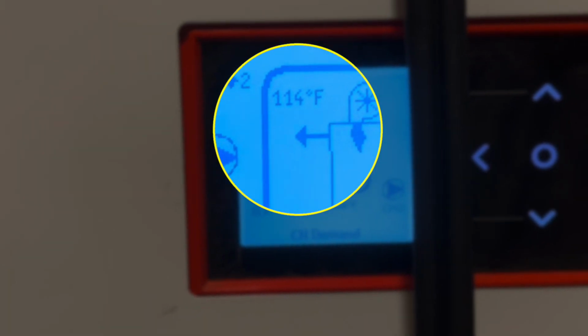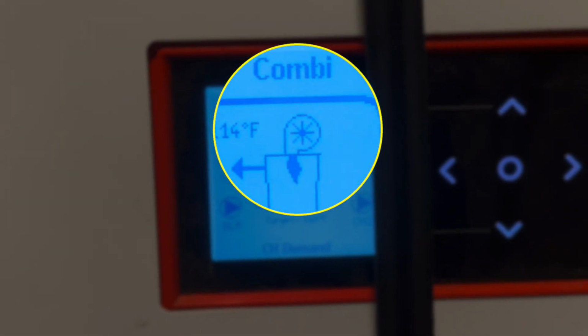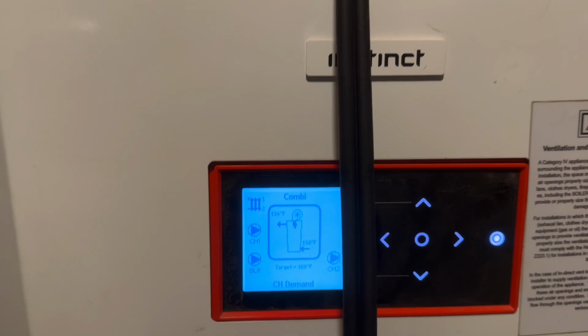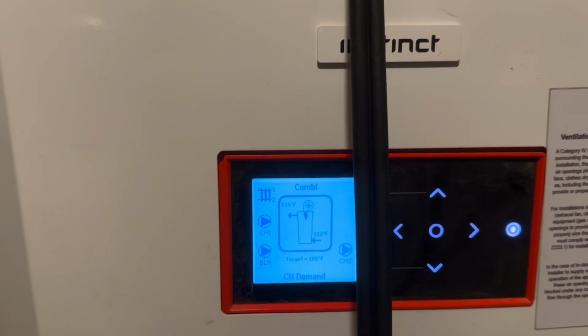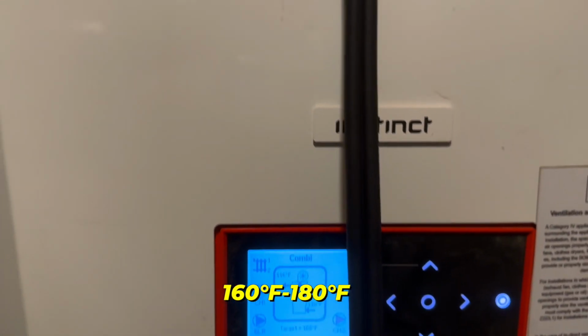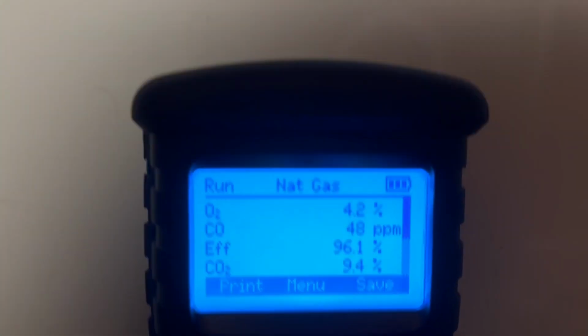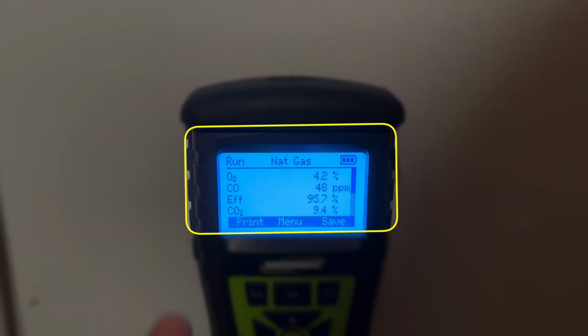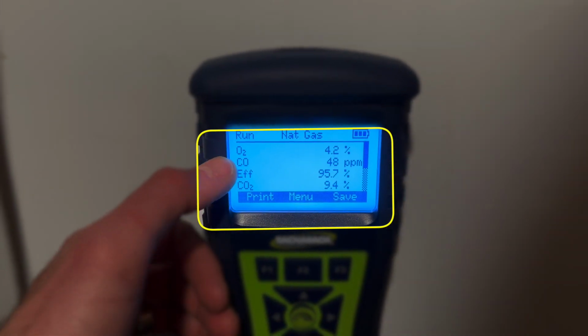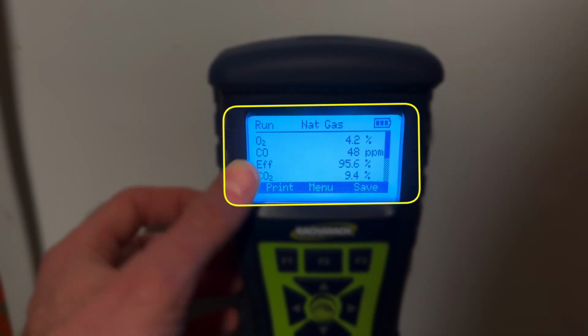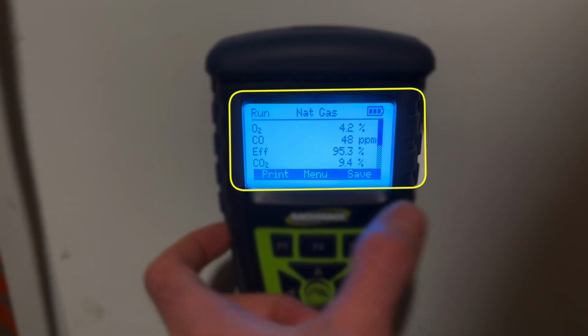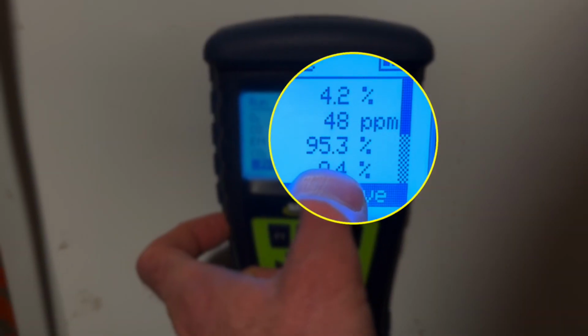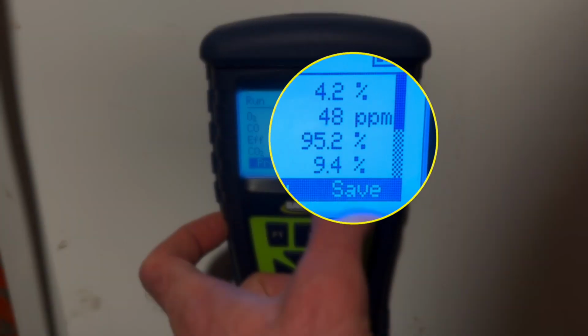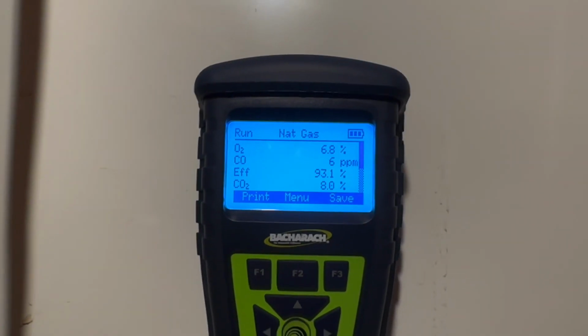So it's firing at 114 on your supply and 106 on the return. And the boiler's actual operating temperature is going to be around 160 to 180, depending on how you have it set up. Typically it's about 180 is what your supply temperature should be. And so as this thing warms up, you can see that the CO numbers, which is carbon monoxide, will come down, indicating a more efficient burn. And as you can see, the actual efficiency it's measuring right now is still at 95%, even though it just fired up. So the system is modulating up and down.